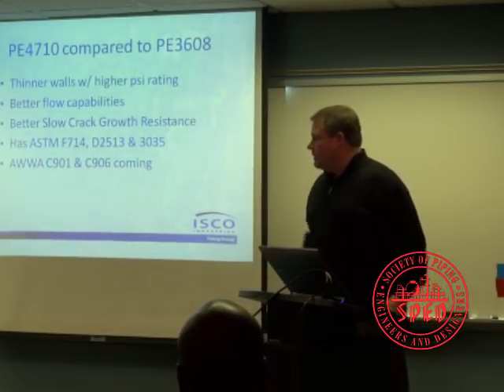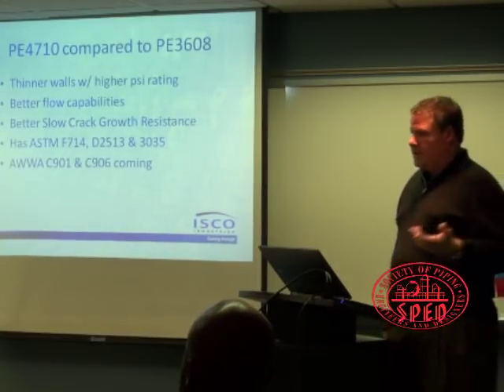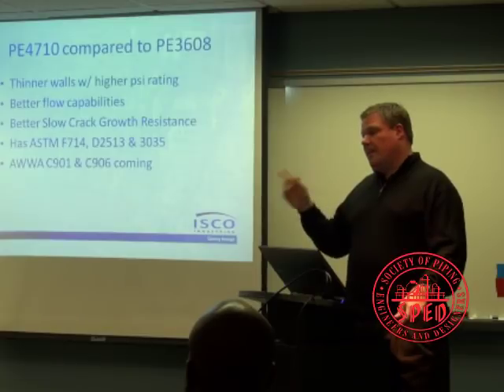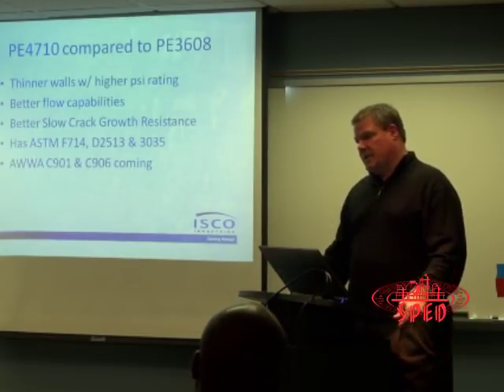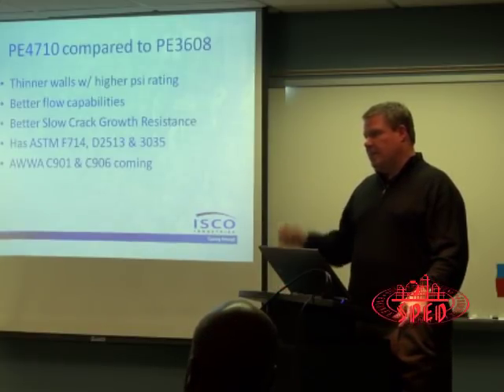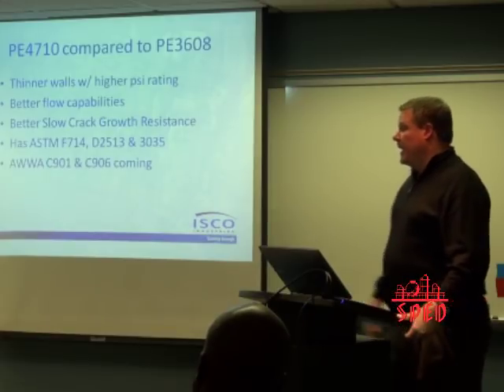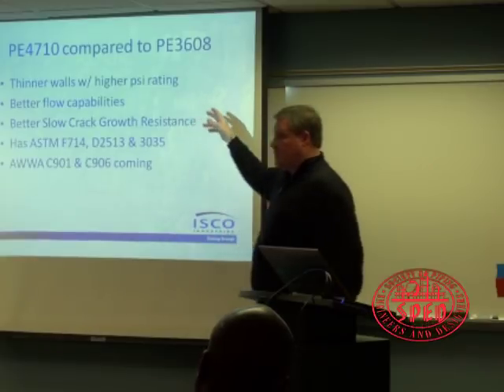We meet all those ASTM standards, and we're currently in the process of getting our C901, C906 AWWA approval. I can tell you right now, everything you're seeing, fitting-wise and pipe, is already 4710 resin, and they dual stamp it with 3608. Just the way it is. And you can take 4710 and fuse it to 3608. You can take 3608 and fuse it to 3408. Same IDs? No, different IDs because less material is needed to get the pressure rating you're looking for.